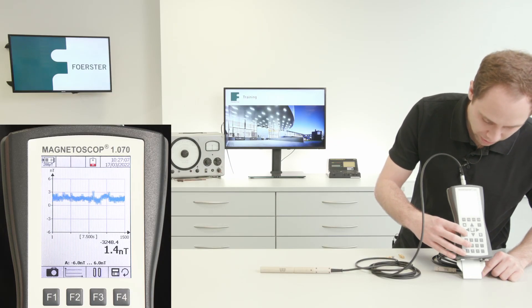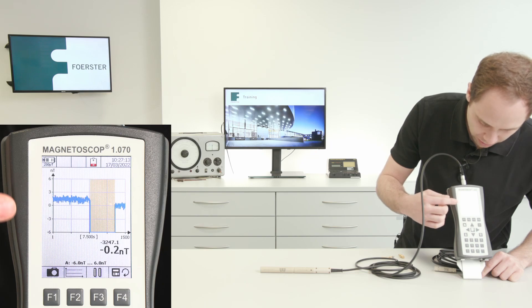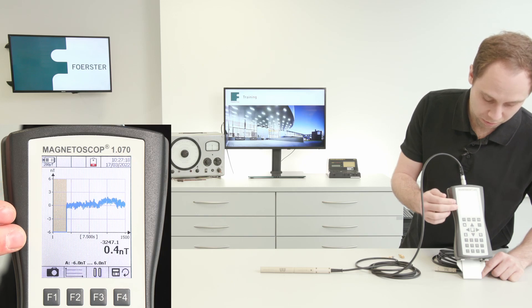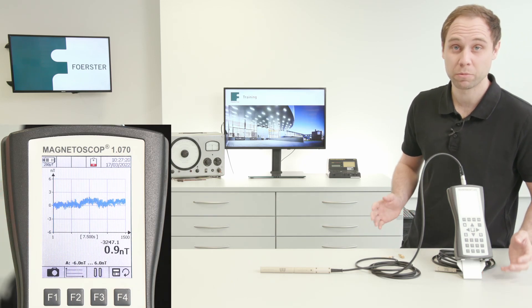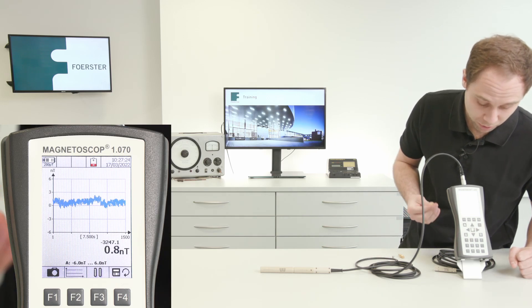Before we start, we should make a zero compensation. Press this button. We make a compensation, and then we should have zero nanotesla on our view. Sure, we still have some disturbing influences, but it is enough for good measurement quality.